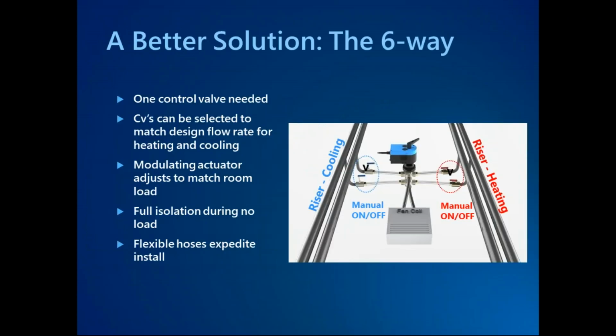So that brings us to a 6-way control valve. And as you can see, the 6-way control valve has gone from having four 2-way control valves on every single supply and return from the risers to a single self-sustaining unit with a single actuator. Now, a 6-way control valve can do either modulating or simple changeover between heating and cooling. There's some flexibility when it comes to install, and we'll look at that a little bit more later. And the CVs can be selected on 2 of those 4 ports to provide that quasi-modulating control that we would be looking for if we were trying to do modulating control for this zone. So all a 6-way is really just a better mousetrap for taking a 4-pipe system and tying it into a 2-pipe zone.